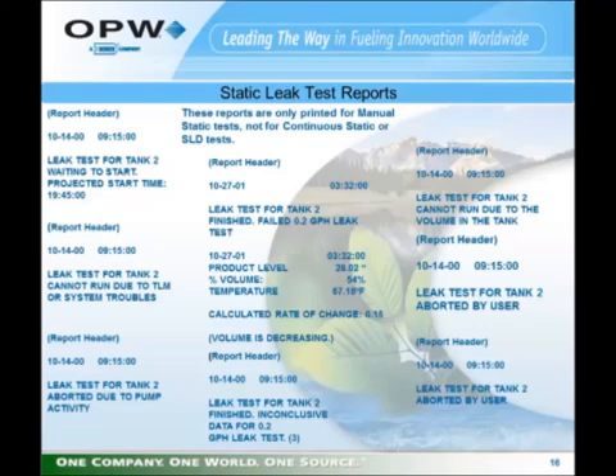Or it will tell you if there's a system or TLM trouble that's going to prevent a tank test from running. If a tank test has started on a manual test and somebody begins using product from the tank, if the system can then identify pump activity, it will abort the test and tell you. It will tell you if you failed a leak test and show you the leak rate. It'll tell you if it's an inconclusive result, or it will give you reasons why the leak test cannot be performed.